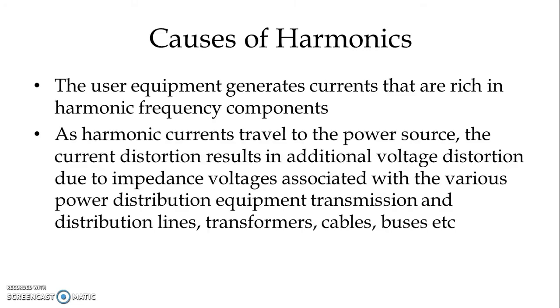As harmonic currents travel to the power source, the current distortion results in additional voltage distortion due to impedance voltage associated with the various power distribution equipment like transmission and distribution lines, transformers, cables, buses, etc. This is known as current distortion transformed into voltage distortion — injected current harmonics. Most of the harmonics are from the load side; currents rich in harmonic components are injected into the power system and through various impedances are transformed into voltage distortion.